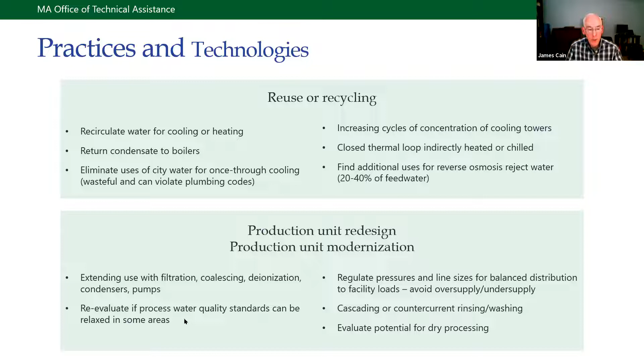Check if the water meters are running. I had one case where a company did that. On a Saturday, someone came in, saw the water meter running, looked around, and finally found a valve that was indicated to be closed but was actually open. So these things happen, and it ties into monitoring and maintenance to check if valves are leaking or heat exchangers are fouled.